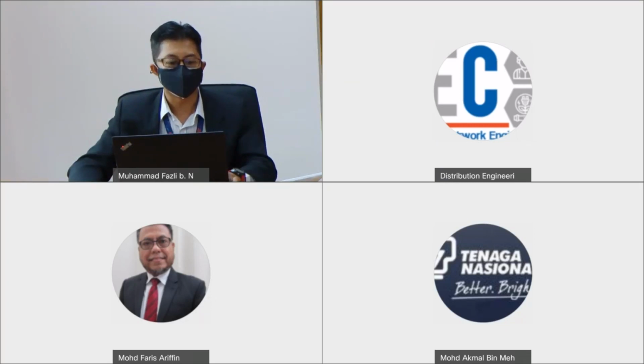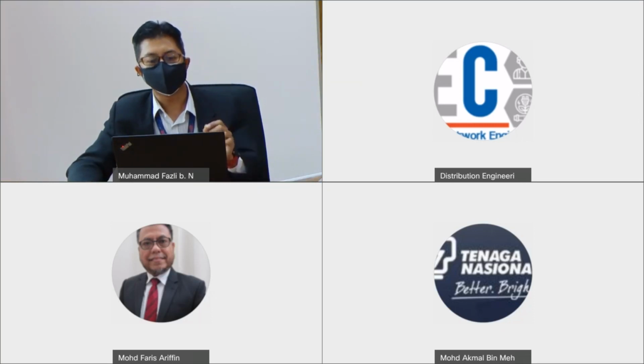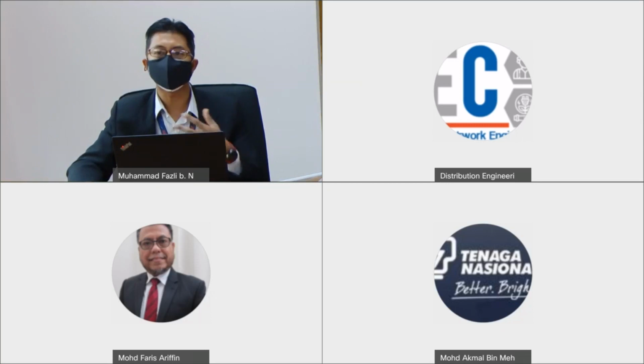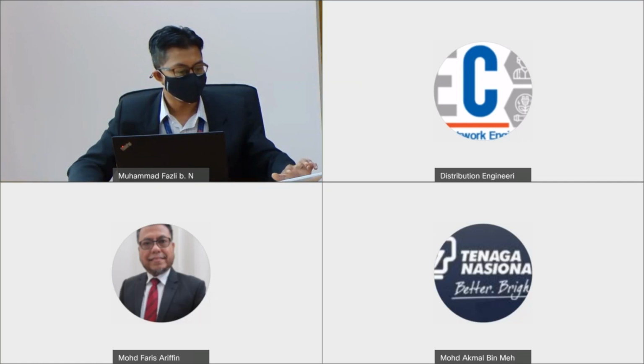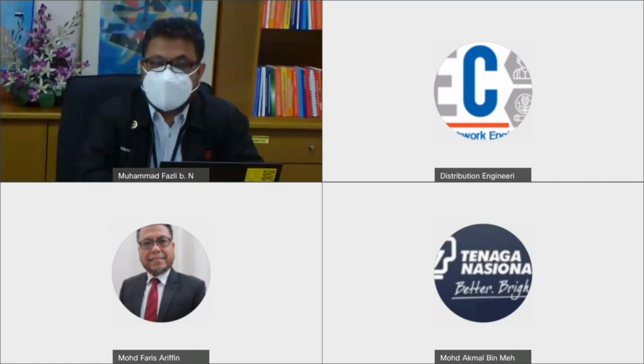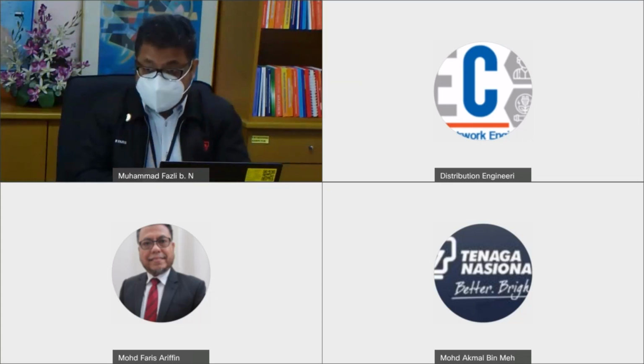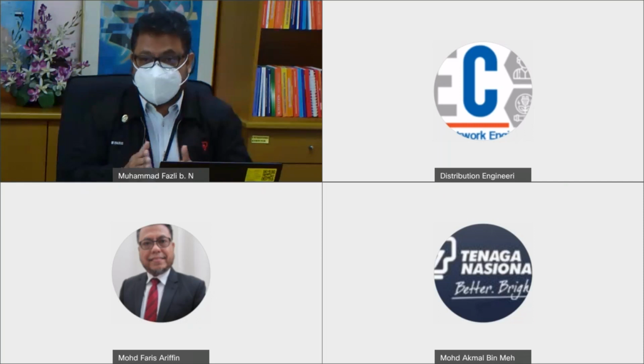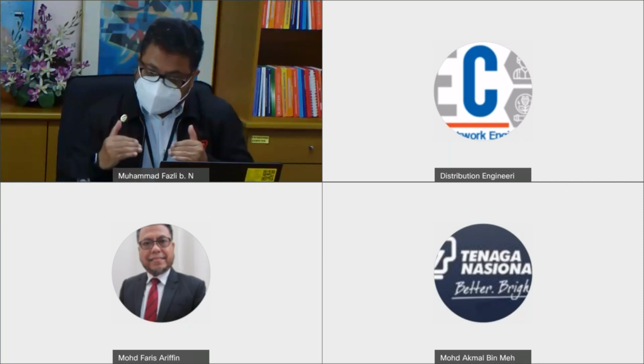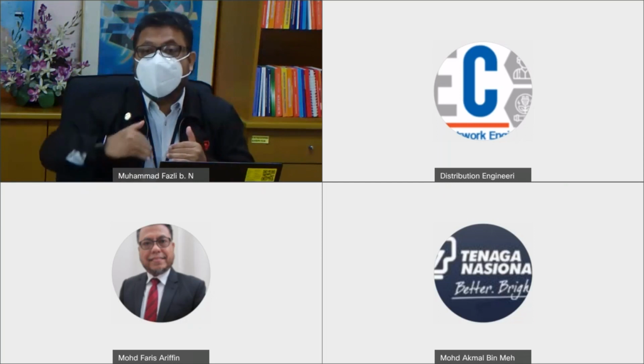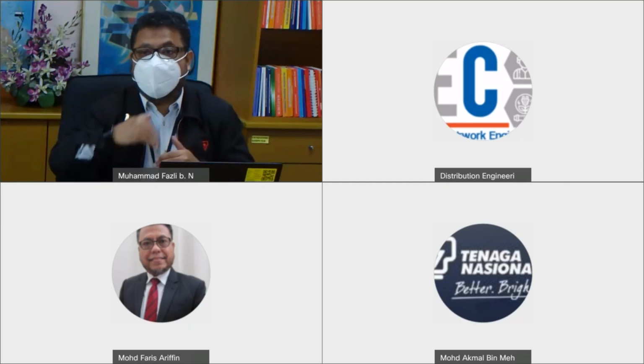So let's go to the next question. The fourth question, from Mr. Razak: what will happen if TFR, tower footing resistance, is higher than the requirement? Is there any possibility that a transient can happen because of the higher TFR? Yes. Due to poor TFR or TFR, the lightning current cannot be effectively dissipated to ground. What will happen? It will go back. It will cause a back flashover.